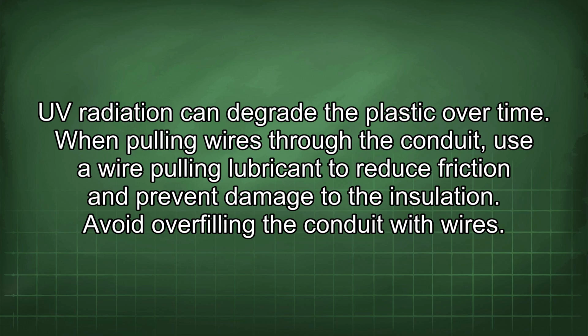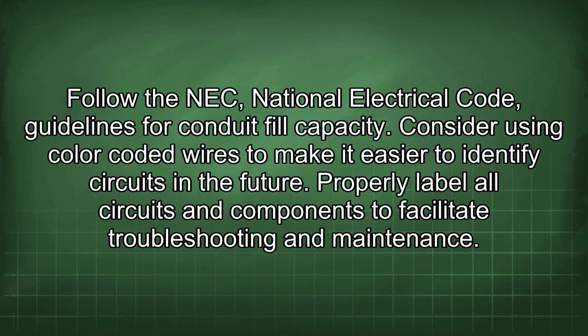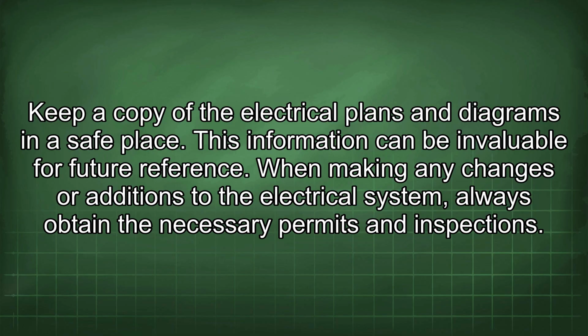When pulling wires through the conduit, use a wire pulling lubricant to reduce friction and prevent damage to the insulation. Avoid overfilling the conduit with wires. Follow the NEC National Electrical Code guidelines for conduit fill capacity. Consider using color-coded wires to make it easier to identify circuits in the future. Properly label all circuits and components to facilitate troubleshooting and maintenance. Keep a copy of the electrical plans and diagrams in a safe place. This information can be invaluable for future reference.